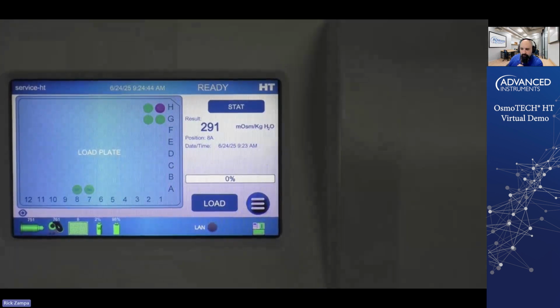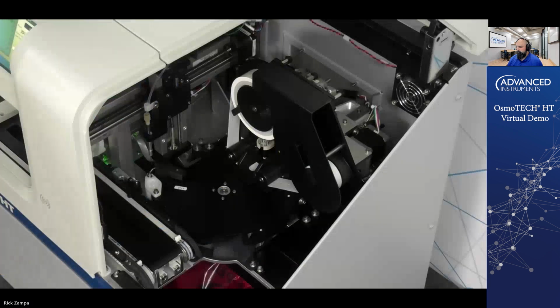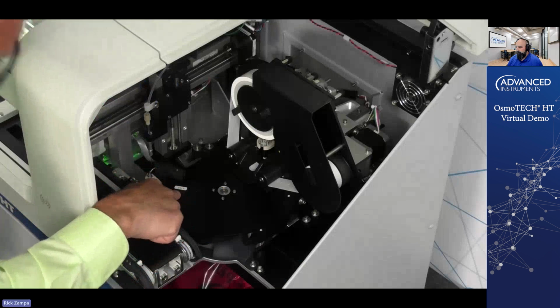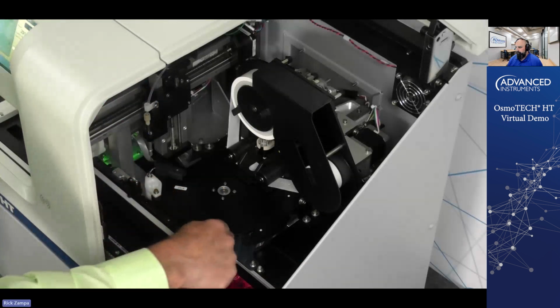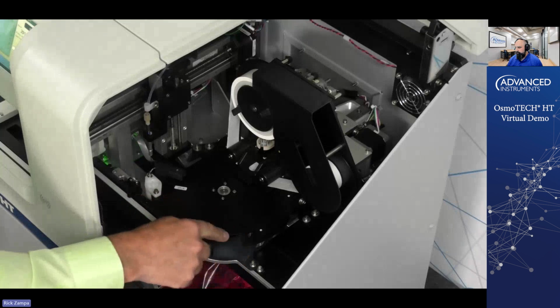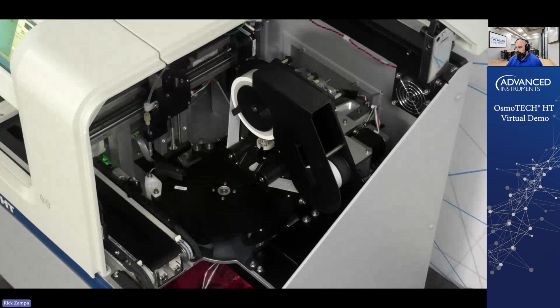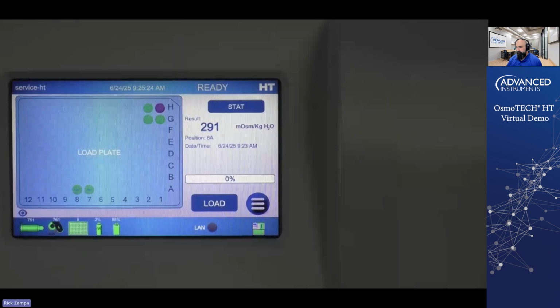We also have a stat function. The stat function allows you to load a sample in that is a rush sample if you need to, while a plate is running. What that allows you to do is, if you hit the stat button, it will finish testing whatever position it's in. And then it will pick up a sample cup, and you can see, I don't know if you can read that there, but that says stat. It will move a sample cup over to this position out here. You'll be able to load the sample into the sample cup, hit the start button, and it will run that sample, and then it will go back and continue running the plate which you have in there. So that's the stat functionality.